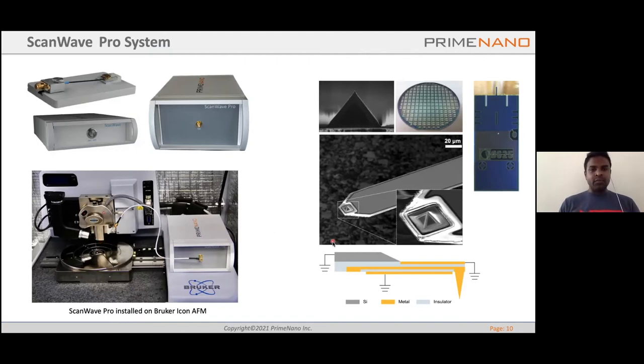These are similar in form factor with respect to the other commercially available probes, but there is one unique aspect to that: the cantilever is completely shielded. The microwaves are passed through the central metal line, and all the sides of the cantilever are shielded with metal, and the microwaves are only passing through this pyramid. And that makes the source of the microwave very tiny. With the tip apex about 10 to 15 nanometers in radius, you get sub 5 nanometers spatial resolution in the electrical properties.